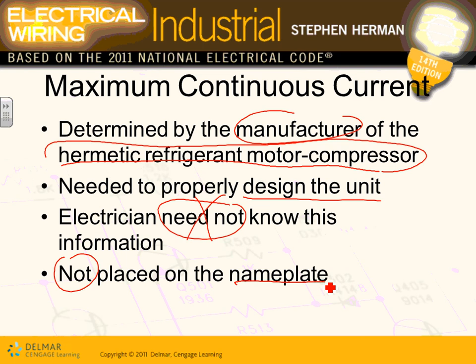So they use it. Typically, guys, this is the highest amount of current that the equipment can run at without burning. So they use it for sizing. So that's a maximum overcurrent protection device. Just FYI, we don't use it for any sizing.